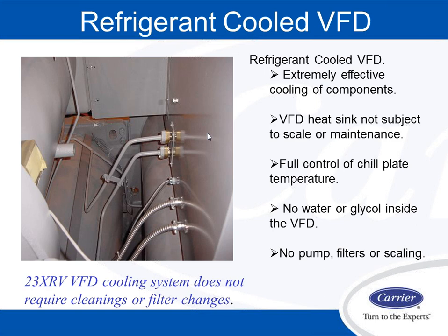I've seen jobs where they have a water cooled drive, and the strainer gets clogged, and when the strainer gets clogged, we have alarms that the drive is overheating, and that requires a service call to go out there and fix the strainer. It's a nuisance for both the end user and the servicing technician. From a refrigerant standpoint, all our losses are included in our selection. So we don't leave our losses external to someone else to handle. All our losses and our true operating kW per ton are in our selection sheet that we send to the contractor, end user, or engineer.